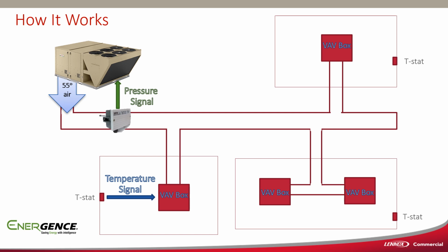Our pressure sensor is going to see that, and our variable frequency drive is going to ramp up or down, trying to maintain a set point for static pressure. So if you put in there you want 1 inch, 1.5, 2 inch, whatever that set point may be, as these boxes open and shut, then the variable frequency drive is going to ramp up and down to try to maintain that set point in static pressure.